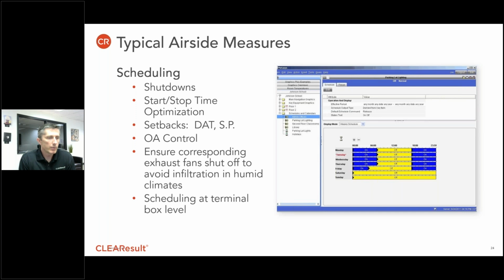On both air side and water side, scheduling is a big opportunity to focus on in retro-commissioning—trying to turn things off or set them back when they aren't needed, when the building is unoccupied or it's not a critical space. You can't save more energy than by turning something off, so we want to identify what can be turned off and how to bring it back on at the right time so people are comfortable when they arrive.